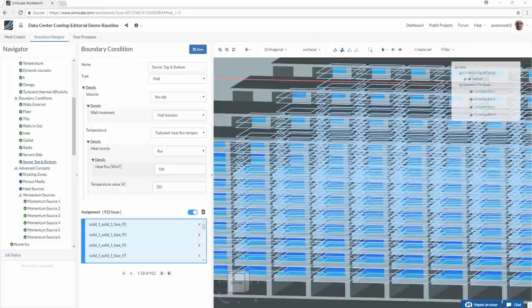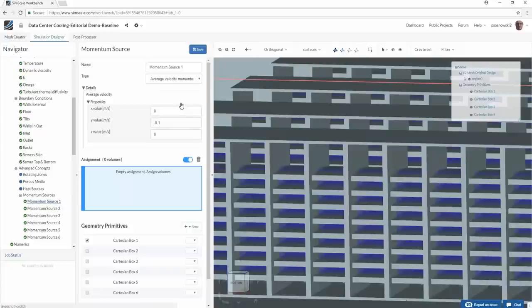There was a question about the CRAC units and the outlet pressure. I think I answered this during the presentation. And also, how do we know the speed of the fan? That's a very good note that server fans can have variable speeds, working faster or slower depending on the performance of the device. So in this particular case, we are using a steady state simulation. So overall, we are considering an operational condition that the servers themselves were working for an infinite amount of time, or sufficiently long time, to establish a certain flow regime.